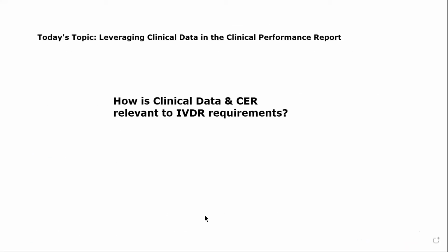Okay, yes. Today our first question is, how is clinical data and clinical evaluation report relevant to IVDR requirements? So I think this is really getting at the question of where do we find information and guidance, because there really is so little IVDR guidance available to us. So really, when we go to MDR, that seems to be what the majority of notified bodies are referring us to, is to go back to the guidance for MDR. And we know that the IVDR guidance is forthcoming.